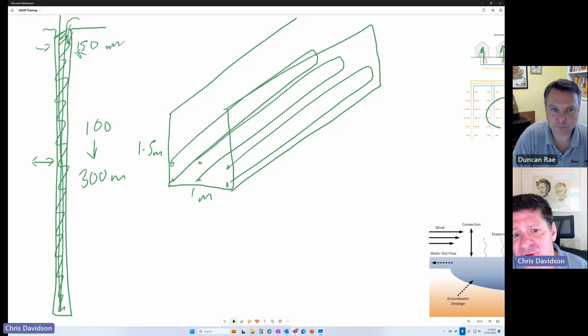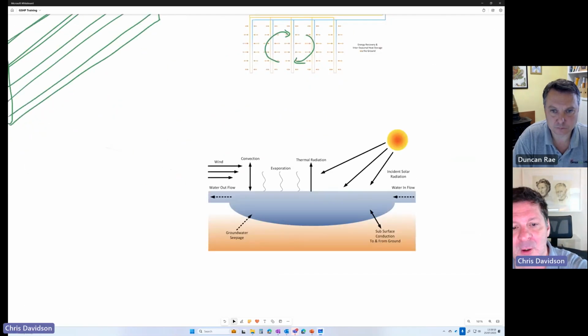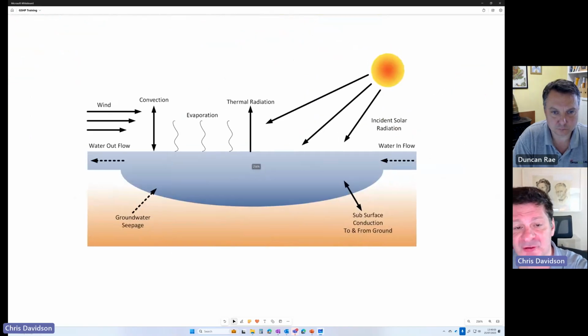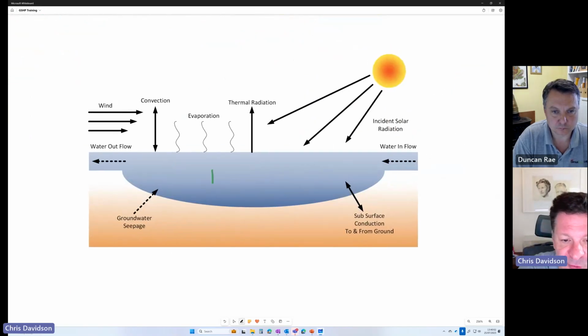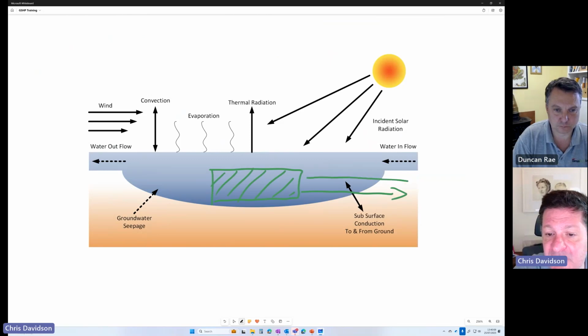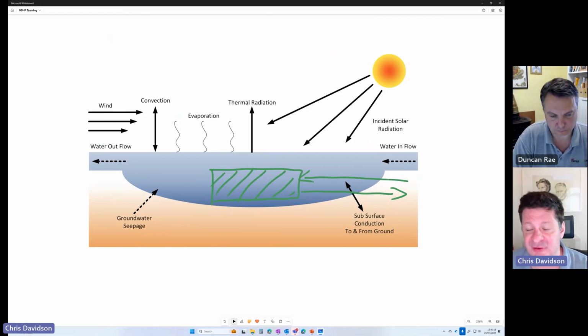We have done them in schools and things like that where you've got playing fields perhaps as well. So that's the second type of closed loop system. So it's a closed loop of fluid, the same fluid circulating around that system all the time. We can then have a look at surface water systems. So anytime we've got some surface water, we can put some heat exchangers into that water, and we can take heat out or put heat back into that water. And as long as we are balancing the heat in and the heat out with natural gains and losses from that body of water, again, we've got that sustainable system.